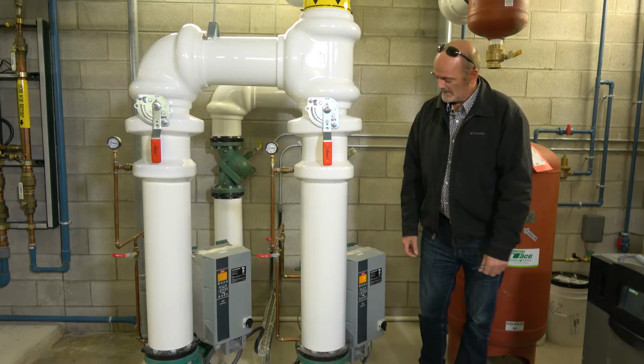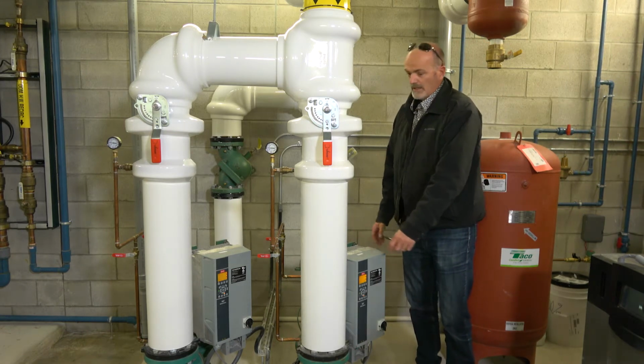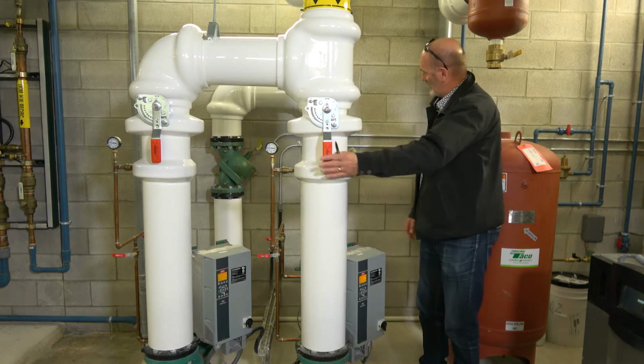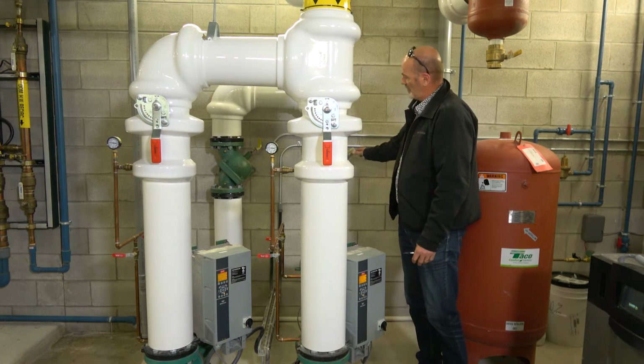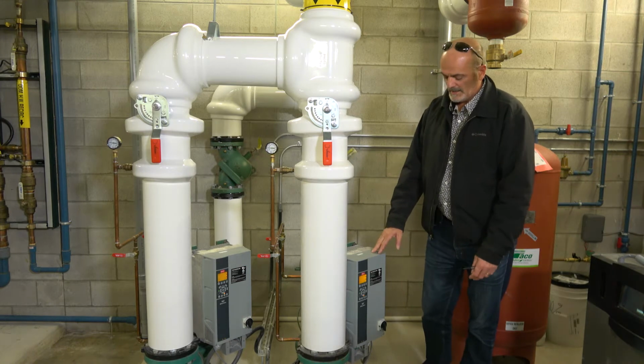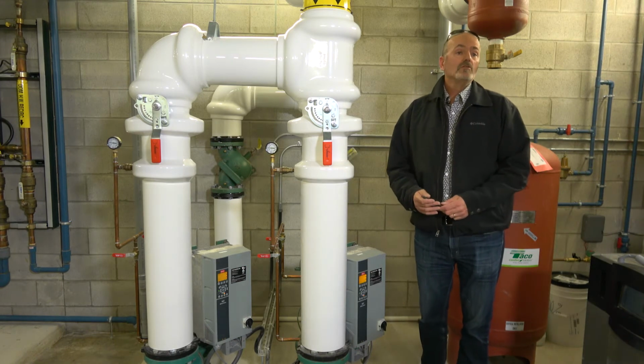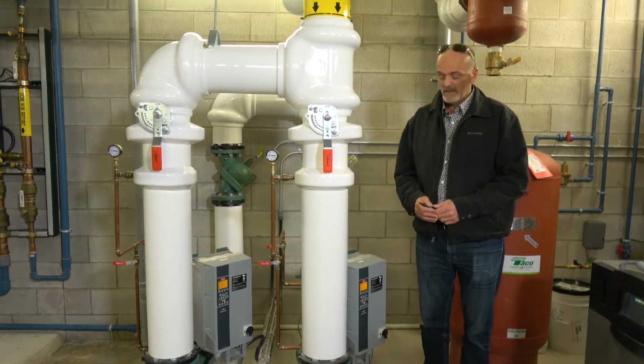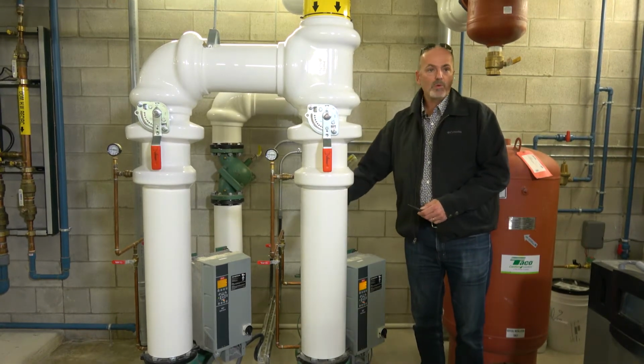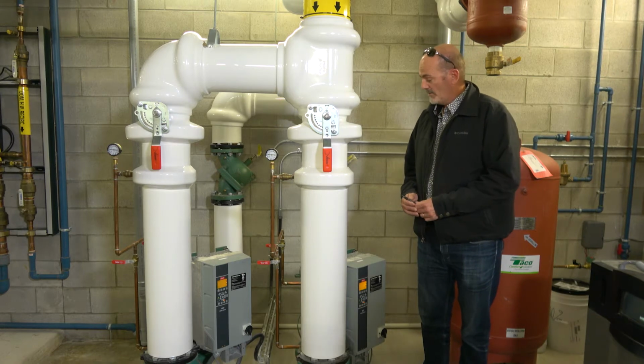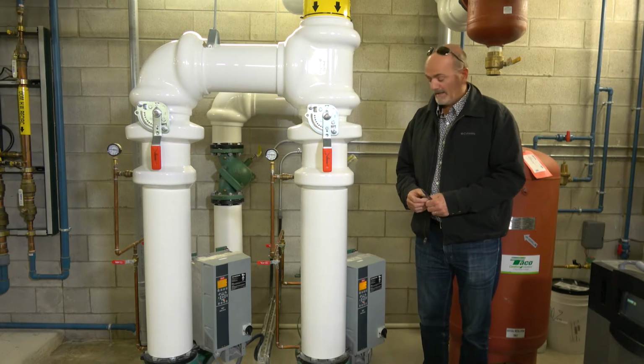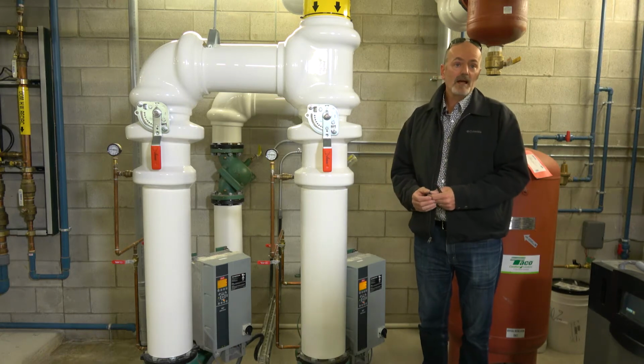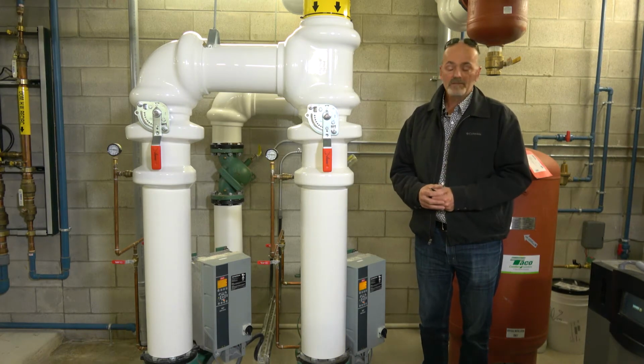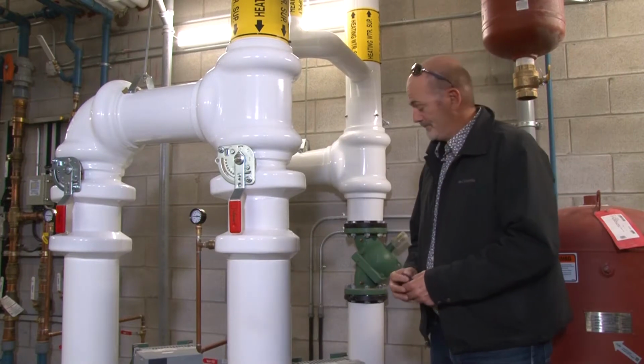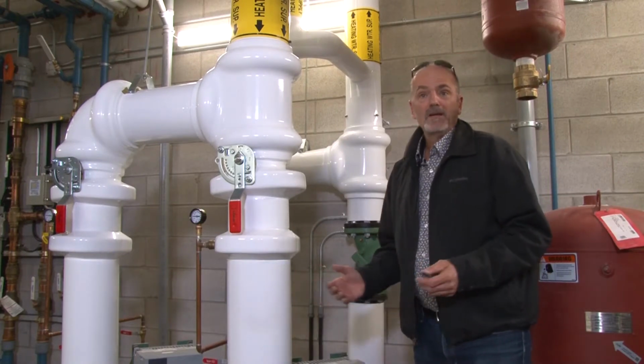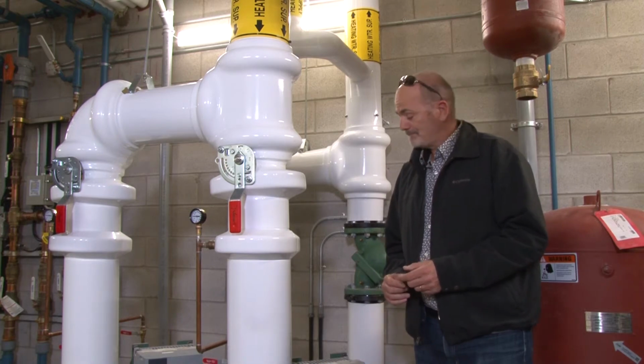It comes in a little box, and then the contractor would come in, isolate on the suction side, and isolate here on the discharge side because this valve can be closed. And then you would allow the system to cool, drain down, change the seal. And the seal gets changed by removing the radial bolts around the base of the motor pump cover bracket, lifting, and then tilting on its side, getting access to the impeller, spinning the impeller bolt off, pulling the impeller, and then changing the seal. Okay, so it's a bit of work involved. So again, it's a contractor deal, right?